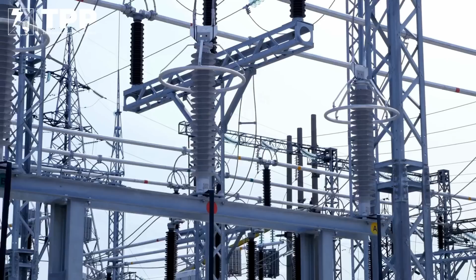So meaning our bulk system, for example, above 100 kV, just making a generalized statement, because those are the bulk assets, and we need to make sure that all of that particular power circuit is maintaining stability for the whole power grid, because otherwise we will have blackouts. So based on that, we have the largest substation because of the larger voltage. And again, I'm presuming we are talking mostly about the AIS, not the GIS. GIS is in the building. So predominantly we are just concentrating on the AIS.